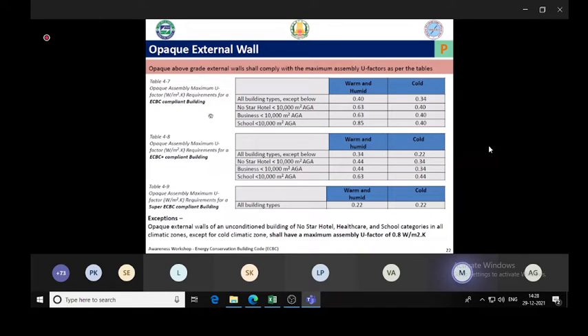So when we talk about an external wall, the ECBC provides a maximum U value to be compliant. For basic ECBC compliance, the maximum allowed U value for an office building is 0.4 watt per meter square Kelvin. Depending on the type of building and the area, the U value is variable. For example, if it's a school building, less than 10,000, then a U value up to 0.85 is allowed, whereas for an office building less than 10,000 square meter, a 0.63 U value is allowed.